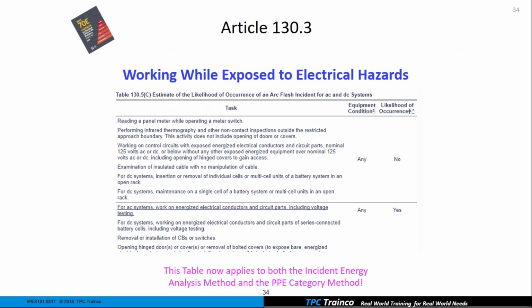So I took a little bit of that table and I wanted to show it to you. 130.5C, this table was also in the 2015 version of 70E. But if we take a look at it now, this does apply to the incident energy analysis method and the PPE category method. In the 2015 version, a lot of people were under the impression that this could only be utilized with the PPE category method. But if I've generated my label with the incident energy analysis method, I can certainly use this table now.